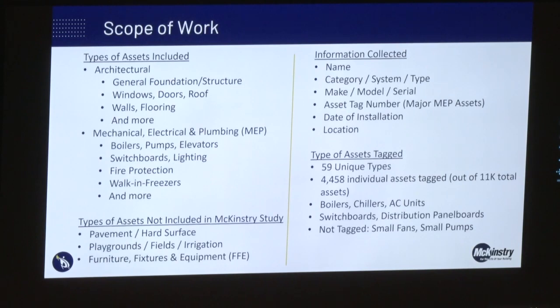There were 59 unique types of assets tagged. We went through this in an exhaustive fashion with staff. In the end, a little over 4,400 individual assets were tagged out of a total of over 11,000 assessed. Primarily big units—boilers, chillers, AC units, switchboards, distribution panels—are typical for tagging, but smaller assets like fans often weren't tagged since they're repaired by replacement rather than maintained, as the cost is too small.